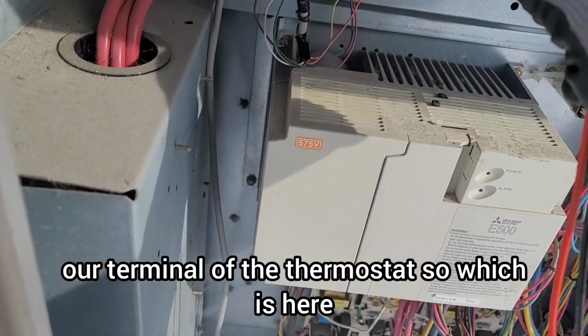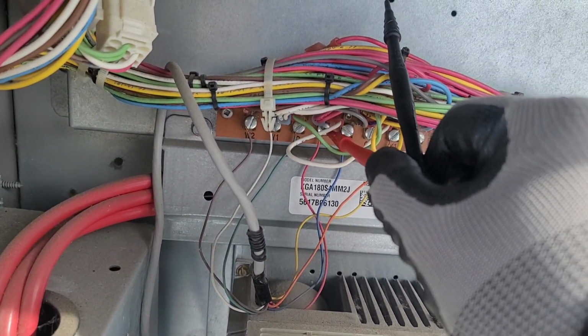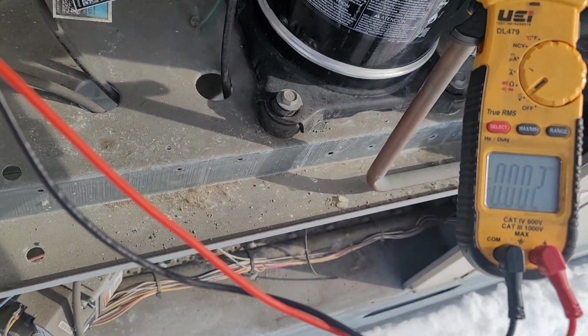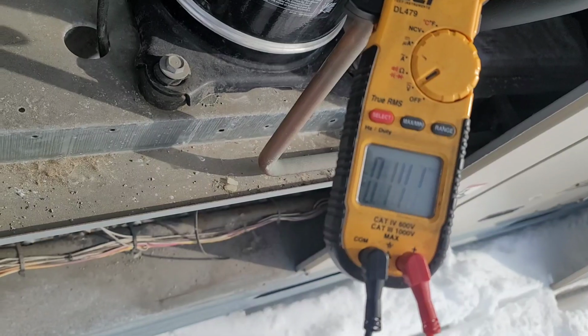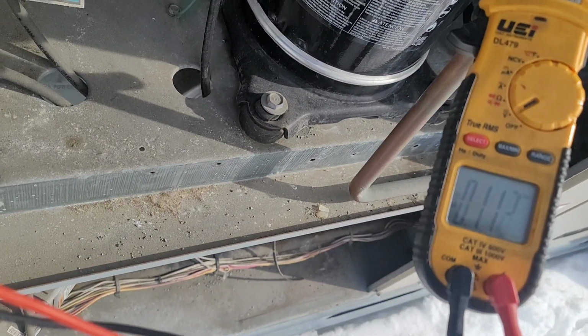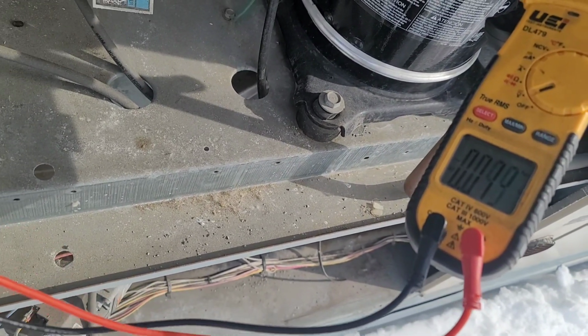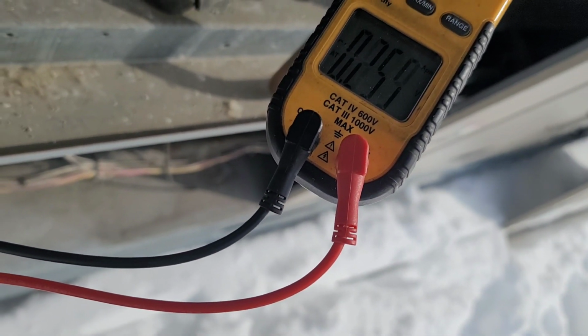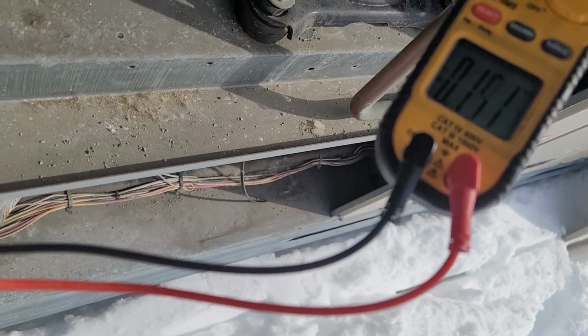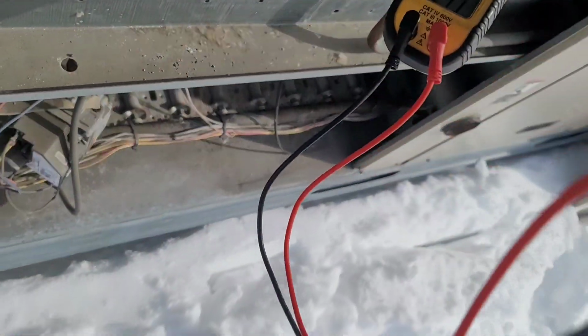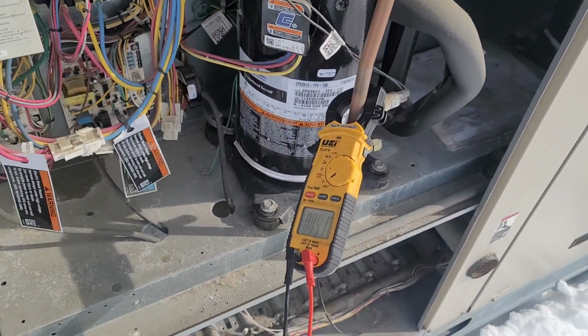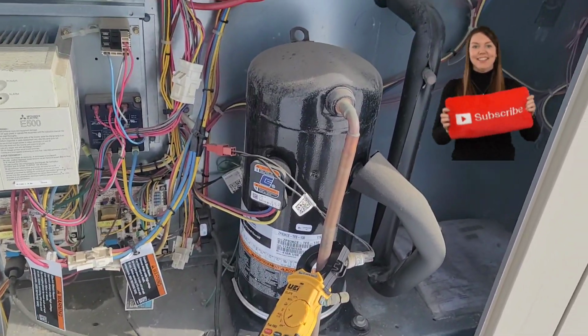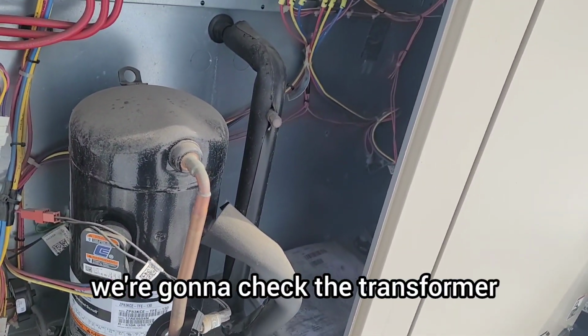terminal of the thermostat, which is here. Zero. Or between R to C. Yeah, nothing. Yeah, nothing, zero. Okay, so we do not have 24 volt. And next thing, we're gonna check the transformer.